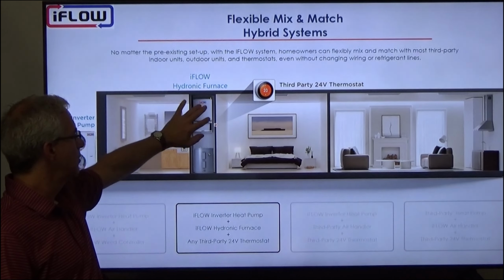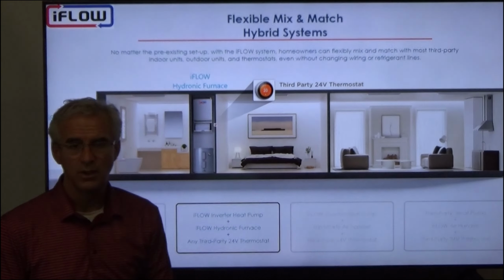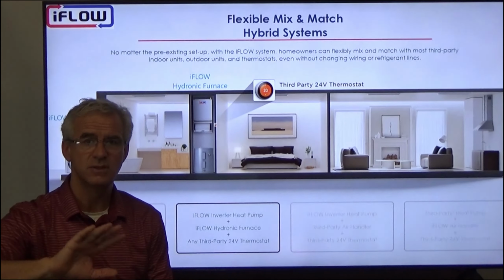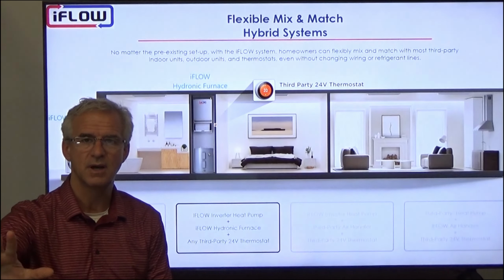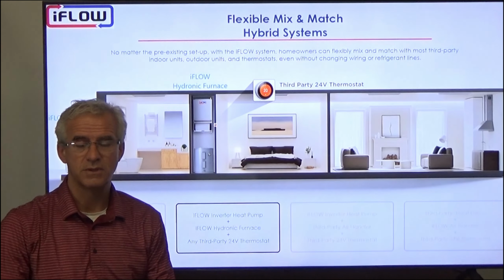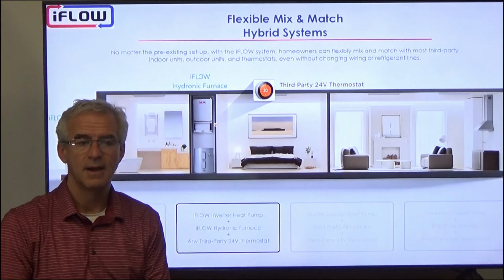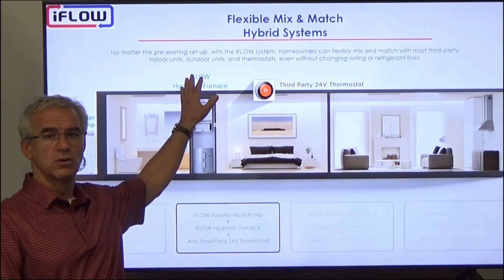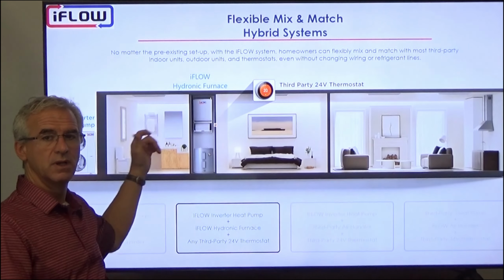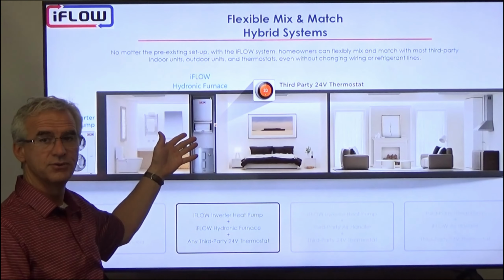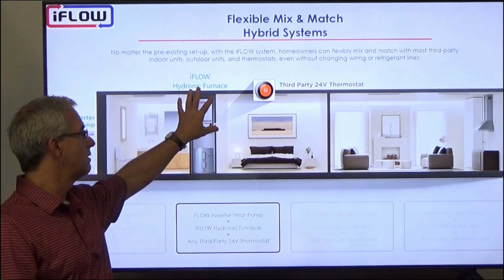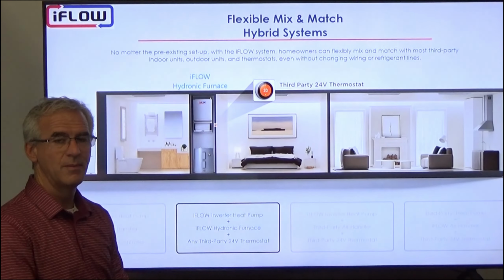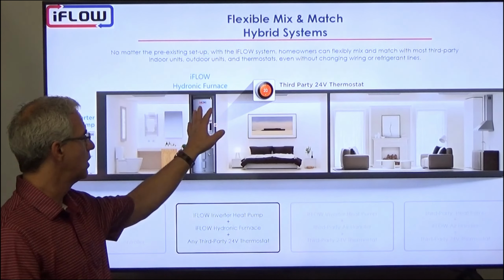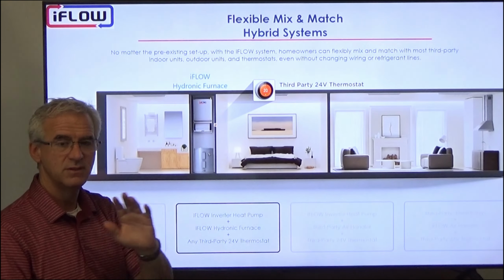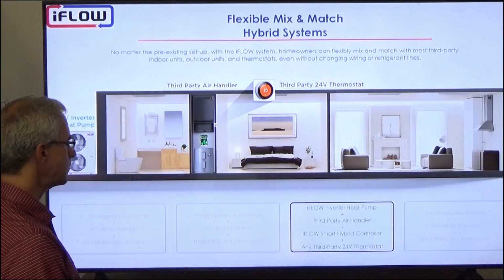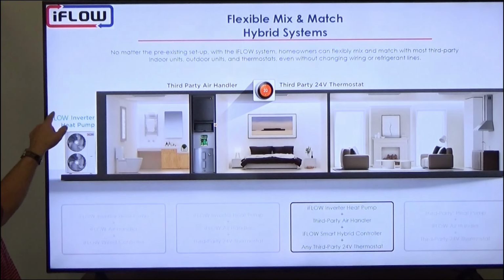If you're using the iFLOW hydronic furnace, then you have the option of using any thermostat you want. It does not have to be a hybrid, or a heat pump thermostat. It can be the simplest, most economical thermostat out there. It just wires into the iFLOW, and then the iFLOW controller will decide: do we run the heat pump or do we run the hydronically based system? And the homeowner can program in some parameters to adjust that switchover point. But all to say, we can run with those third-party thermostats without problem, and they do not have to be heat pump thermostats.